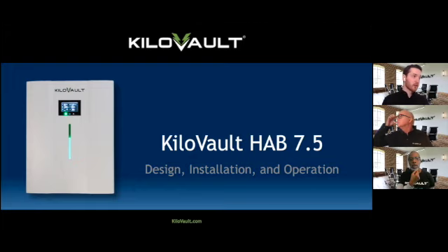Lithium ion versus lithium iron phosphate. It's a good question. We didn't really touch on the chemistry in this presentation, but it is a lithium iron phosphate battery. Lithium ion is a catch-all for a number of different lithium chemistries. So when we talk about lithium iron phosphate versus lithium cobalt oxide, for example, those are both lithium ions. We employ a lithium iron phosphate chemistry for a number of reasons, principally due to safety. There's no risk of thermal runaway with lithium iron phosphate batteries. They're also a fairly low cost and high cycle life solution. And that's why we use that as opposed to others like lithium cobalt oxide.